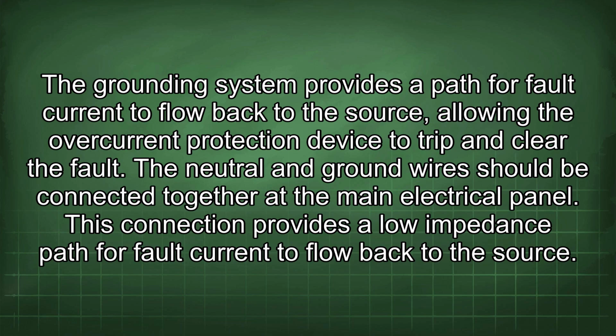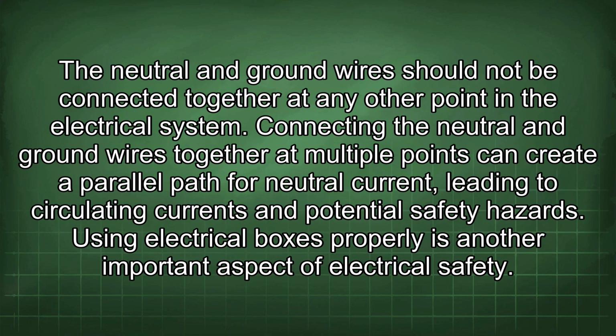The neutral and ground wires should be connected together at the main electrical panel. This connection provides a low impedance path for fault current to flow back to the source. The neutral and ground wires should not be connected together at any other point in the electrical system. Connecting the neutral and ground wires together at multiple points can create a parallel path for neutral current, leading to circulating currents and potential safety hazards.